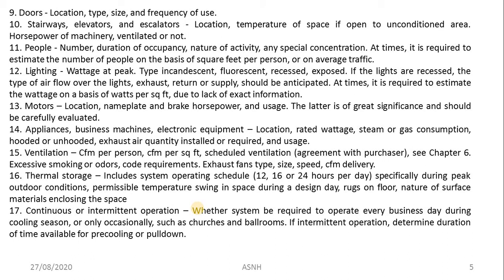The fifteenth important aspect is ventilation. We must consider CFM per person, CFM per square feet, and scheduled ventilation. We must also consider excessive smoking or odor code requirements, and exhaust fan type, size, speed, and CFM delivery. CFM plays a very important role in the case of the AHU — the air handling unit — and we must consider the type of fan, their speed, and their relevant parts.